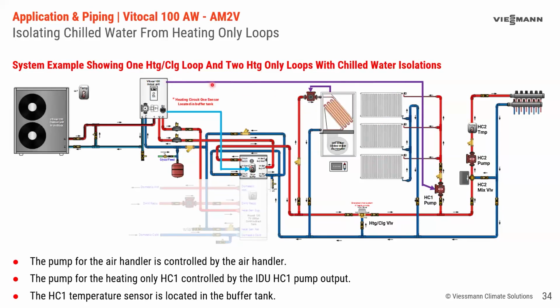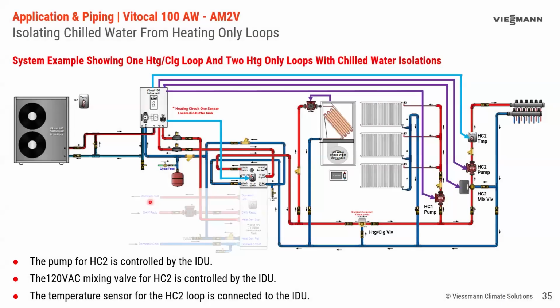And this logic is going to be whether the buffer tank is hot or cold. It's going to be based on that temperature sensor in the buffer tank, which is, remember, circuit 1, and the setting of the control, which is set for heating mode, right? The heating and domestic mode. And then we have the second circuit. So in this case here, we have circuit 1. It's going to run its own pump for the panel rads, and the air handler is going to run its own pump internally.